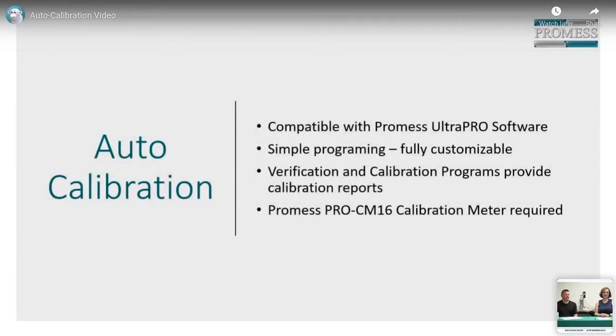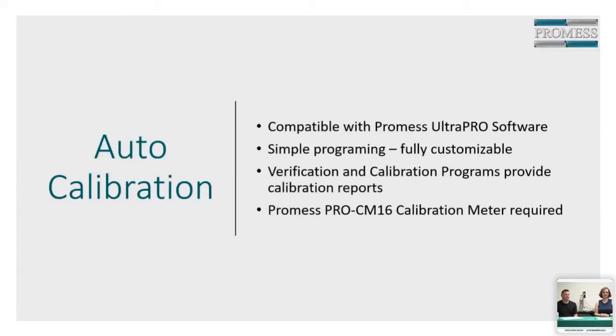To go into a little bit more detail, we have a video that we're going to show you. The auto-calibration has been added in the Ultra Pro software and features the same fully customizable programming structure as the standard Ultra Pro part programs. The user can determine how many points of verification are needed, as well as the force increments in which the verification is performed. The user can also choose how many force points the UltraPro takes into consideration when making an adjustment. The auto-calibration program will automatically generate a verification or calibration report that compares the verification points the user has defined to the user-defined tolerance. The reports are saved locally on the controller as a PDF and can be referenced or exported for future viewing. The Promess Pro CM16 calibration meter and load cell are required for auto-calibration.